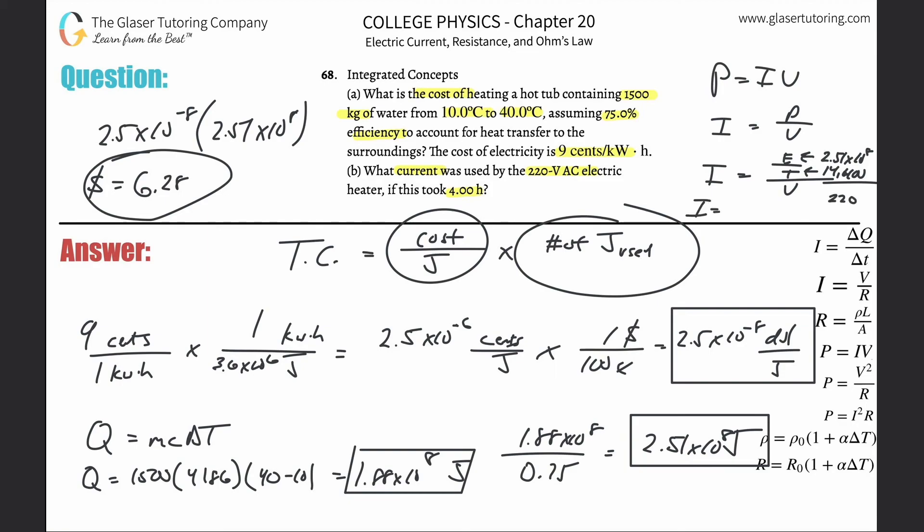So the current here finally is going to be 2.51 times 10 to the eight divided then by 14,400, and then divide that by 220. So 79.2. So 79.2 amps. There you go, guys. Thank you so very much for tuning in. Hope this helped. Please remember to help us out and subscribe. We'll see you soon. Take care.